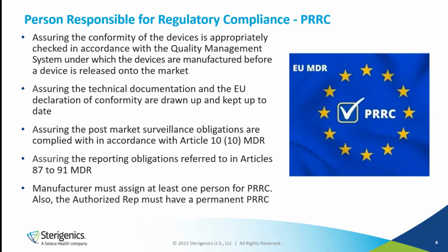A person responsible for regulatory compliance. This is definitely a new addition to the regulations. Now there is a requirement that each manufacturer has a person responsible for regulatory compliance, and their job is to ensure conformity is checked throughout the life cycle of the product. And they're responsible for ensuring that the technical documentation is up to date, the manufacturer is following the post-market surveillance activities, and all of those are being performed as expected.